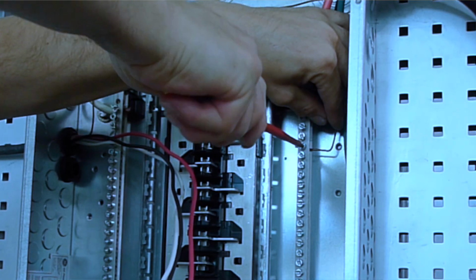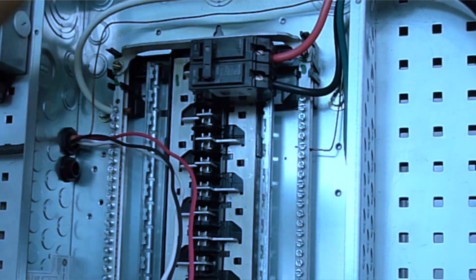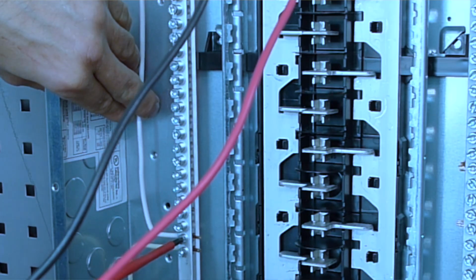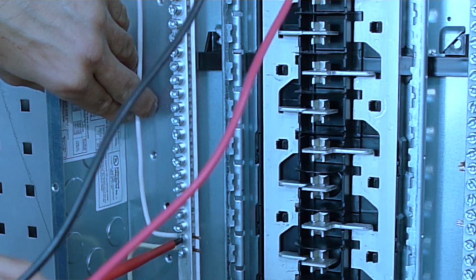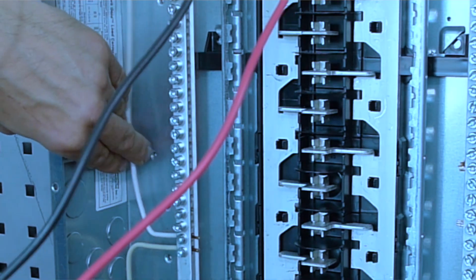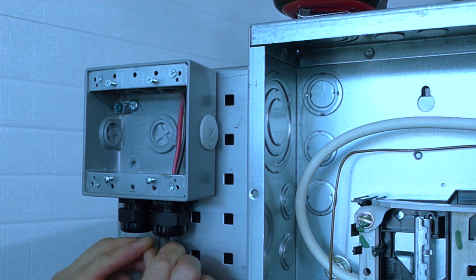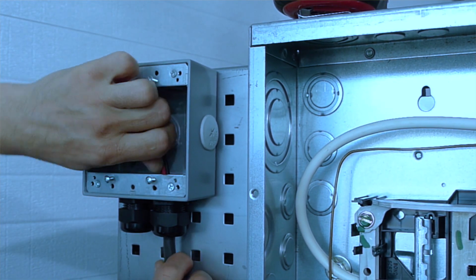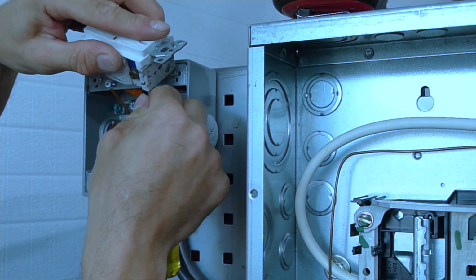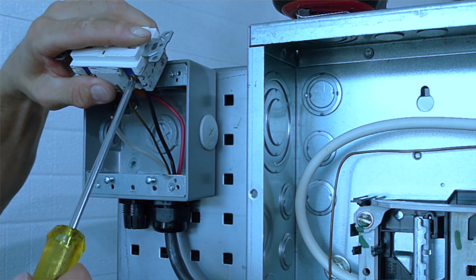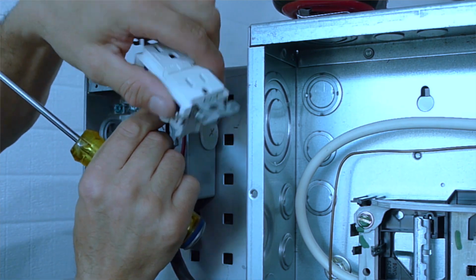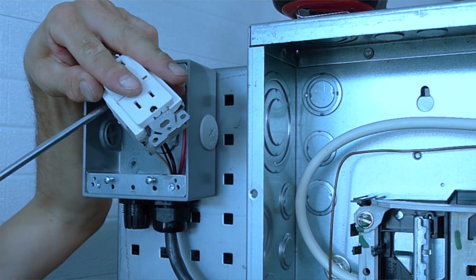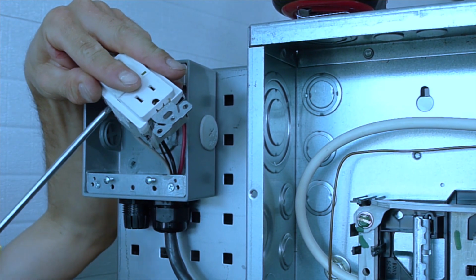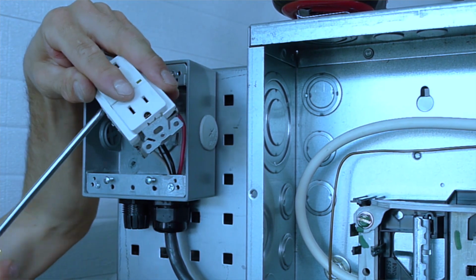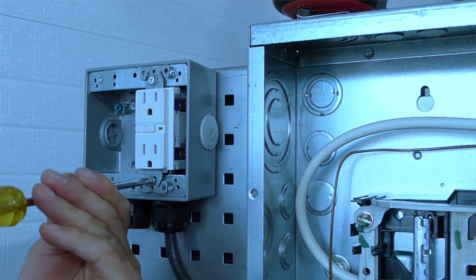Here we are connecting the wires the same way, bare wire to ground, white wire to neutral, and the black wires will be connected to the breakers. We are not connecting the red wire at this moment. I suggest to install wires with extra conductor to each location in the house as well. Just in case anything happens with one of them, the only thing needs to be done is to connect the other wire at the receptacle and the panel.